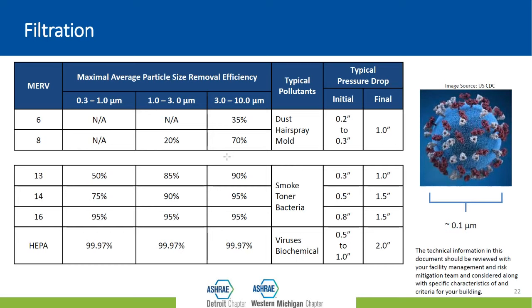And as that resistance increases, it impacts the ability of the fan to operate, right? And we can see here that typical pressure drops for the MERV 6 or 8 filter are going to start off somewhere around 0.2, 0.3 inches, and they're going to end up around an inch. The MERV 13 filter starts around 0.3, maybe 0.25 inches, and when it's dirty, it's going to be around 1 inch. The HEPA filters, however, you can see significantly higher pressure drop with those filters. So the cost, not only for the filter, is going to be more, right, but the cost in energy use for that type of filter is going to be more as well. And let's see how that's going to play out in our system.